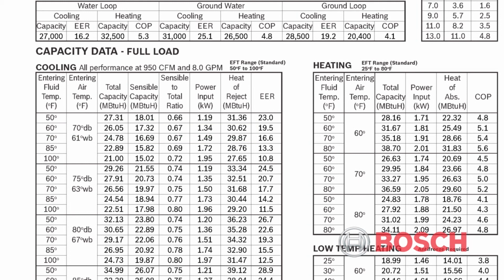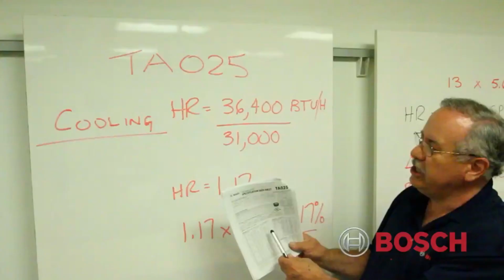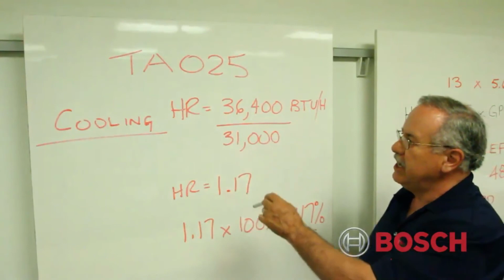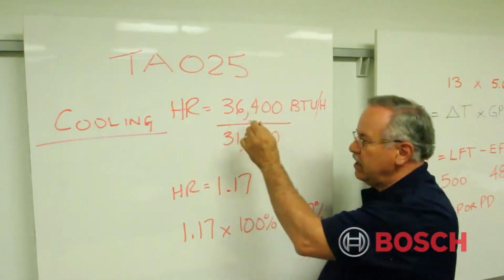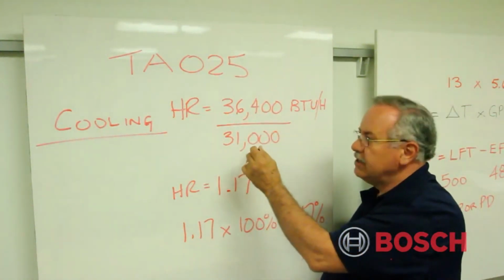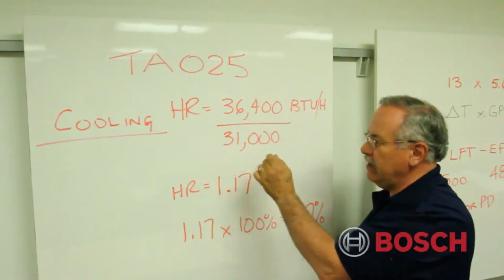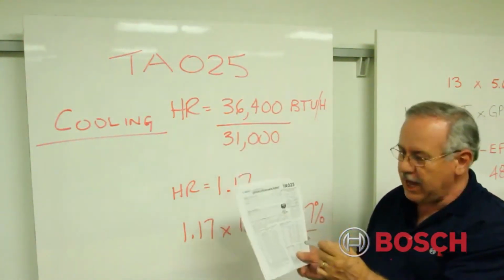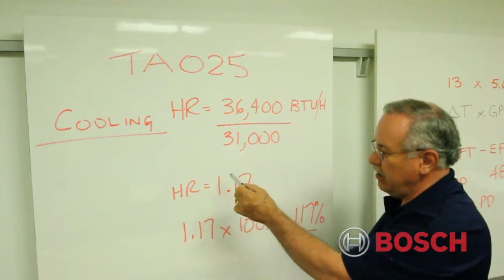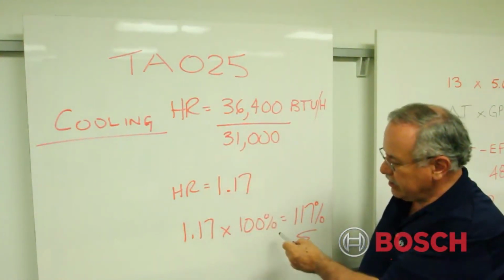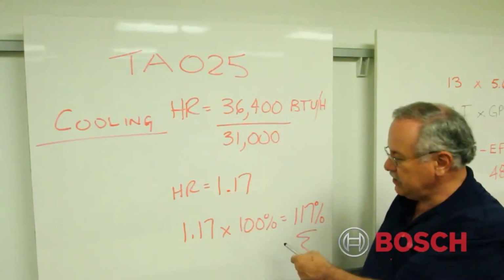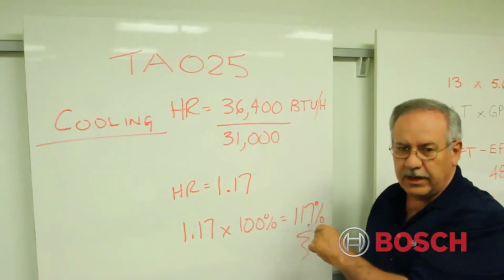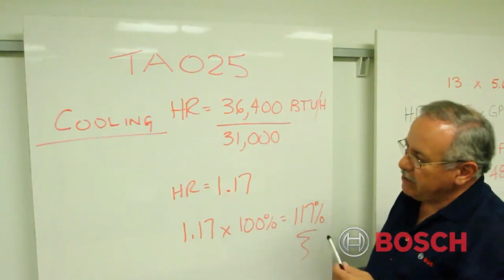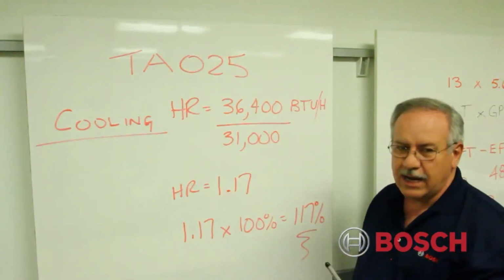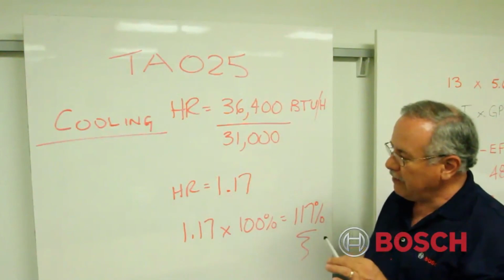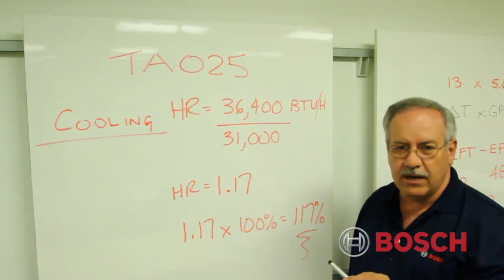heat rejection. So the way to determine how well this machine is running at these particular conditions is what we found, actual, divided by specified. So actual at 36,400 divided by approximately 31,000 from the specs, and we come up with an answer of 1.17. We convert that to percentage by multiplying by 100%, and we are operating at approximately 117%. The Bosch criteria for cooling or heating is a minimum of operation of approximately 90% or better.